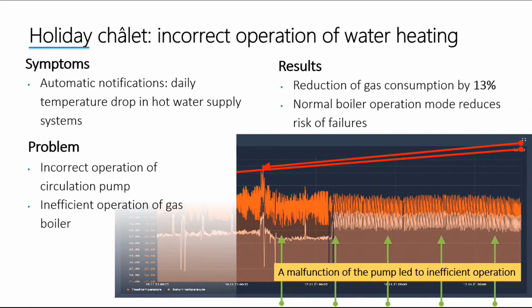Something was wrong with the operation of the gas boiler. But again, from the owner's standpoint, everything was good, the temperature was fine, there was hot water, so no problem from that standpoint. But the system realized there was an issue with operation of the boiler. We found the issue was with the pump circulating water in the heating system, and because of that the boiler operated incorrectly and was overheating water. This was a really interesting issue that allowed us to reduce gas consumption by 13%.